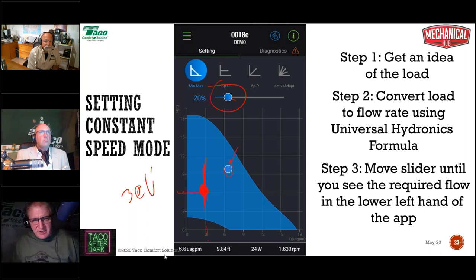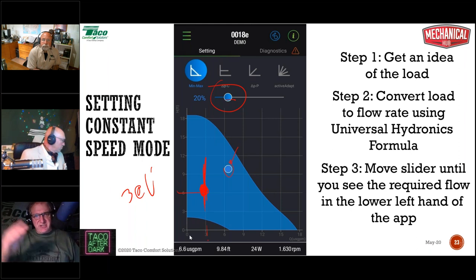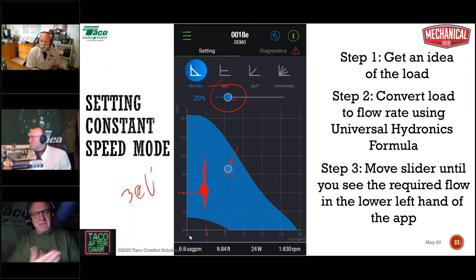And down at the bottom here, where you see the readout, it's going to show 3 gallons a minute at 6 feet of head, and it'll tell you the current wattage. So all that information pops up once you set it up. So if you know the load, you can set this pump up about as well as a fixed speed pump can be set up. Under design conditions, the pump's performance curve has been moved to meet the system requirement, which is all you can do with a fixed speed pump. So just think about how easy that is.